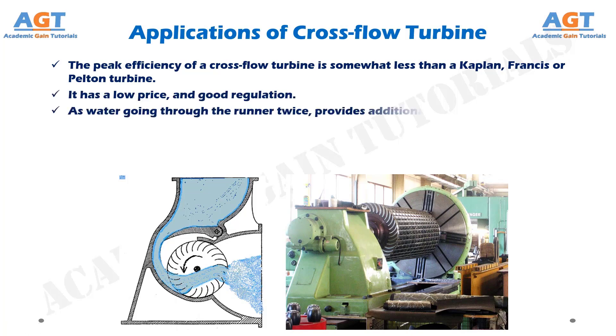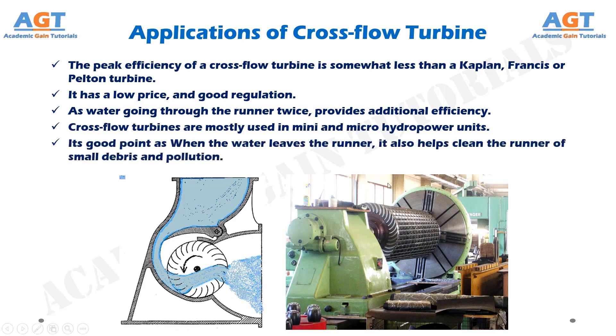The peak efficiency of a cross flow turbine is somewhat less than a Kaplan, Francis, or Pelton turbine. It has a low price and good regulation. As water goes through the runner twice, it provides additional efficiency. Cross flow turbines are mostly used in mini and micro hydropower units. A good feature is that when the water leaves the runner, it also helps clean the runner of small debris and pollution.